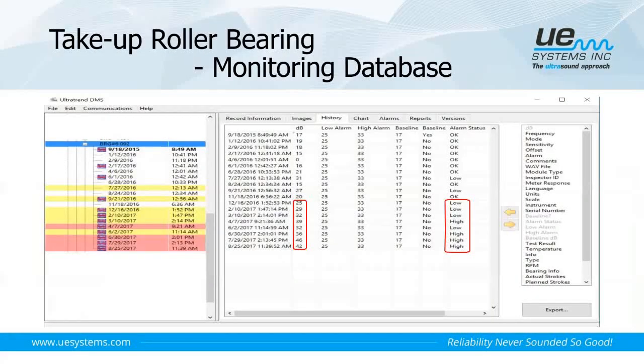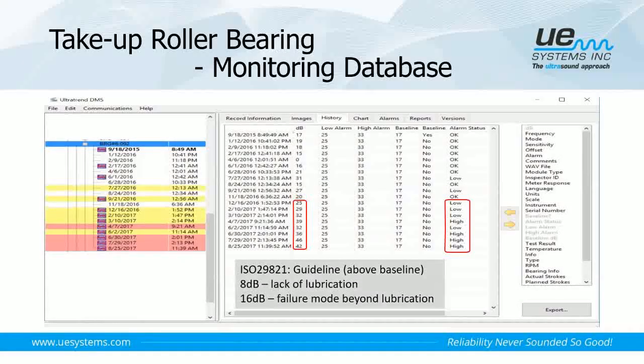Now we will proceed to conveyor bearing monitoring. These are take-up roller bearings. A routine condition-based monitoring practice is applied on these take-up roller bearings. The monitoring database was started in 2015 to 2017, with a baseline of 17 dB in September 2015. The alarm level was set according to the ISO 29821 guideline, with 8 dB above baseline as low alarm and 16 dB above baseline as high alarm. That means 17 plus 8 becomes 25, and 17 plus 16 becomes 33.